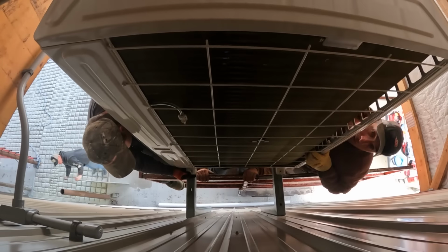But actually the main reason is that we just needed to get it out of the way so that the entry to this part of the building wasn't affected by the unit. There just wasn't a great place to put it, so we put it up super high. And this actually created an interesting scenario where the unit has less clearance above it than is recommended in the instruction manual. And I did clear this with Cooper and Hunter just to kind of ask them about it, and apparently it's actually not that the unit won't function properly, it's just for serviceability, having a little bit more space above it would have been really nice. However, this was the best we could do, and it ended up working out really well.